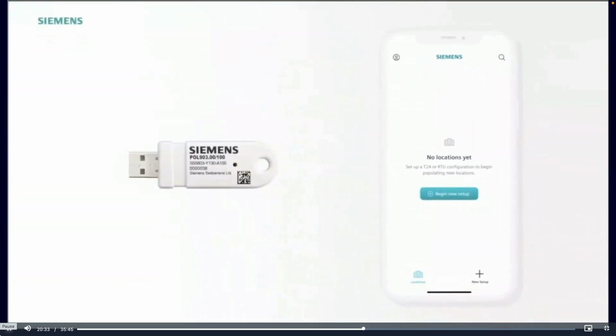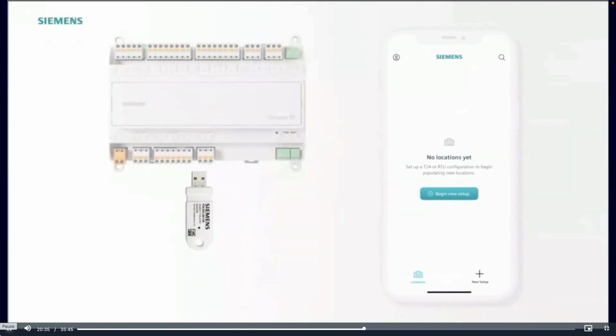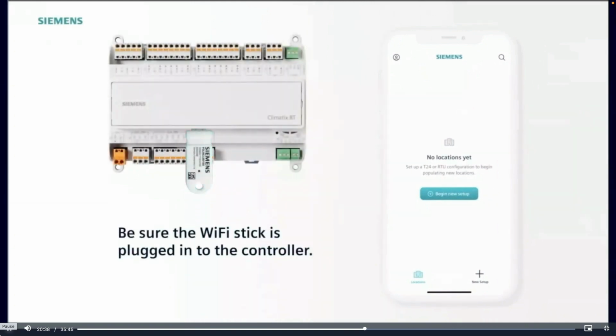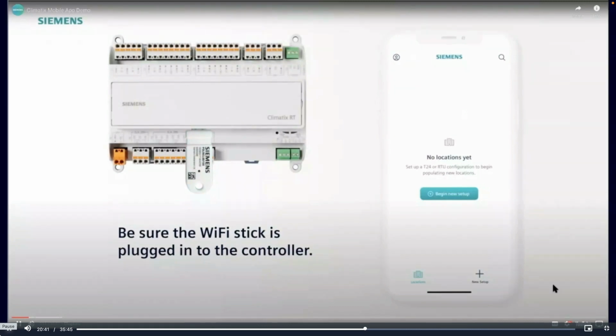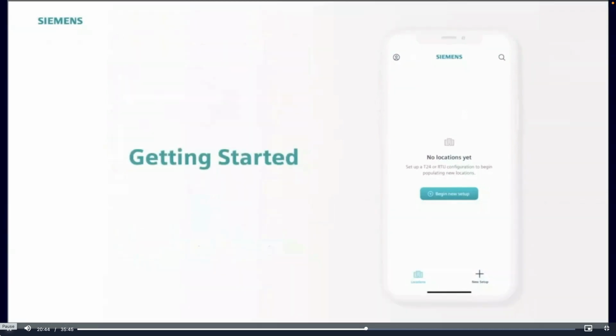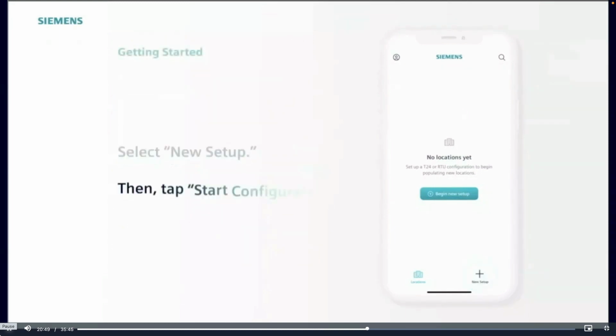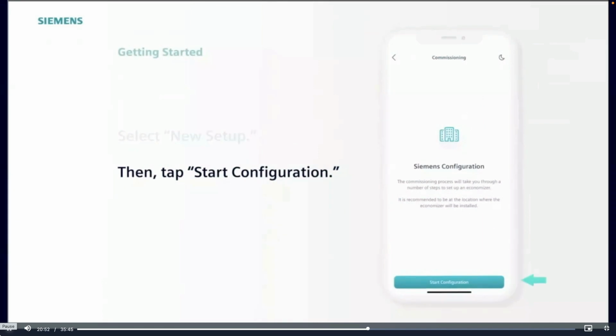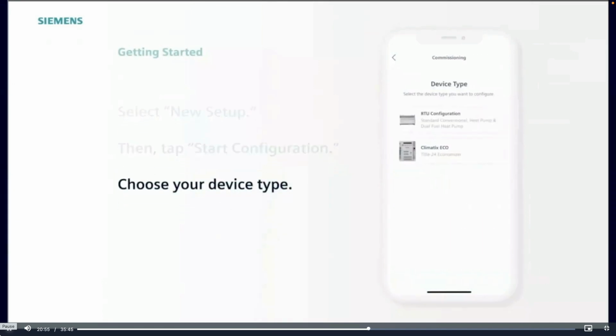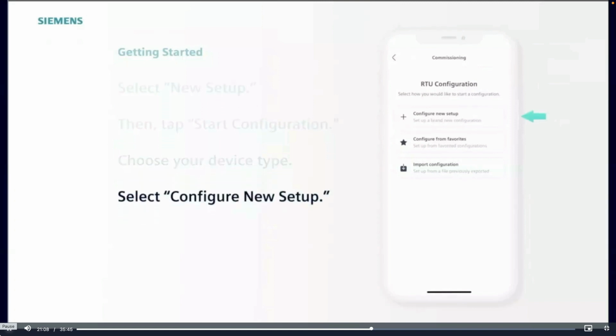This is an overview of the Climatix mobile application. Before we start, make sure you have your Wi-Fi stick plugged into the controller. This is a secure point-to-point connection that will allow you to apply your preferred configuration to your setup. Let's get started. First, select New Setup. Then, at Siemens Configuration, tap Start Configuration. First, pick which type of device you are setting up. For this example, we'll select RTU configuration. There are three options to start: Configure New Setup, Configure from your favorites, or Import Configuration. First, select Configure New Setup.